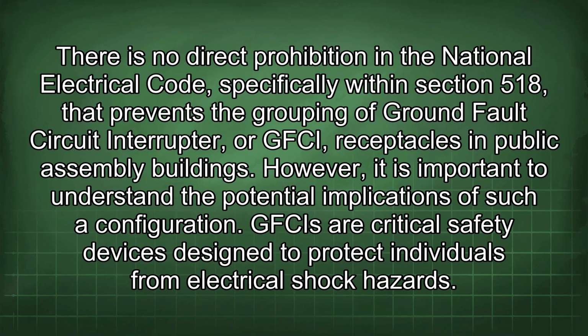There's no direct prohibition in the National Electrical Code, specifically within Section 518, that prevents the grouping of ground fault circuit interrupter, or GFCI, receptacles in public assembly buildings. However, it is important to understand the potential implications of such a configuration.